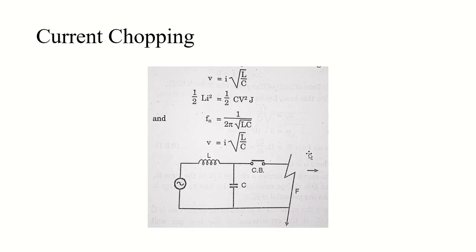Now there is a topic called current chopping. Current chopping is basically the phenomenon of current interruption before the natural current reaches zero value. This occurs mainly in air blast circuit breakers, because the air blast circuit breaker retains the same extinguishing power irrespective of the magnitude of the current to be interrupted. When interrupting low inductive current like the magnetizing current of a transformer, a rapid deionizing effect causes the current to fall to zero before the natural current zero — this phenomenon is called current chopping.